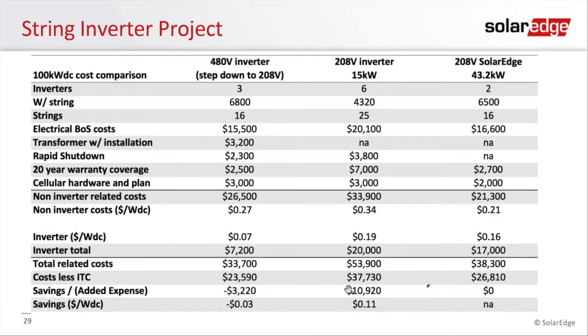And then even as you look at the 480 application, which has the same number of strings, 16 versus 16, you have that extra transformer. So despite the fact that those inverters are fairly low cost at 7 cents, there really is only about a 3-cent gap or advantage to the 480 application versus SolarEdge 208. So that's on the CapEx side. Here we haven't taken into account any of the other value items, some of which I talked about already.